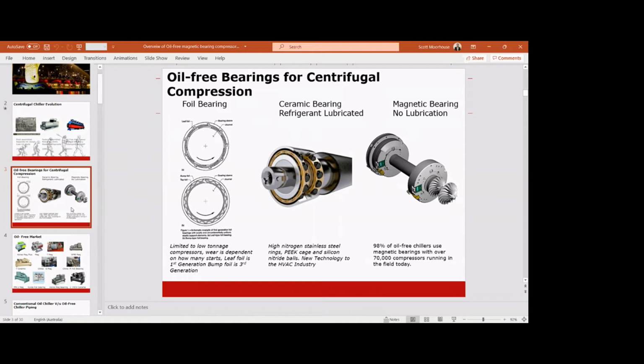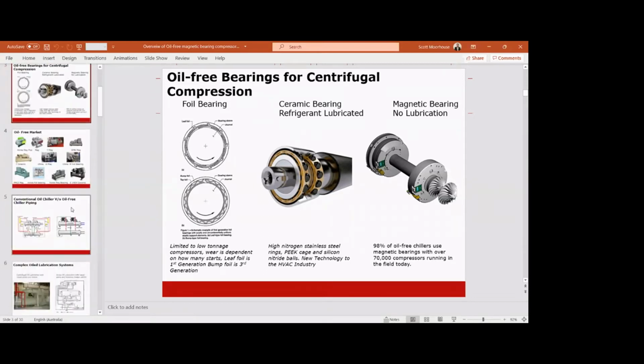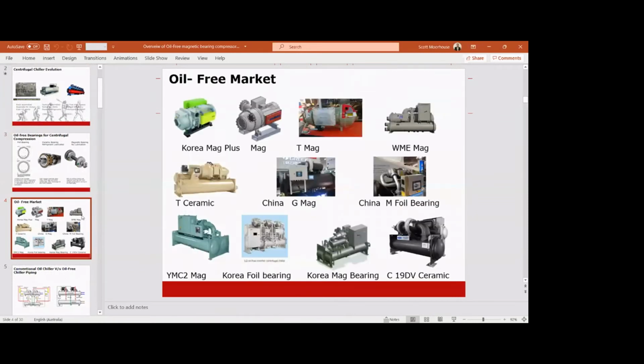And then there's the magnetic bearing. So 98% of oil-free chillers are using magnetic bearings today, with over 70 to about 80,000 compressors in the field running today on magnetic bearings.